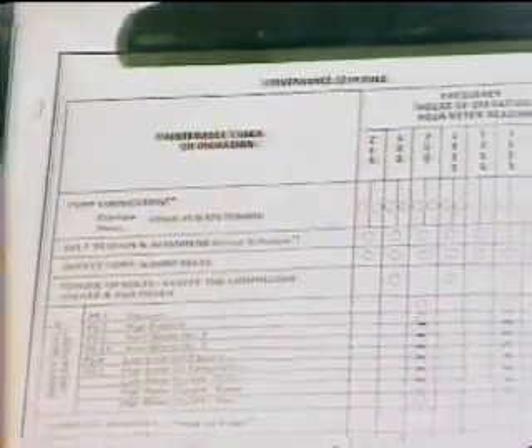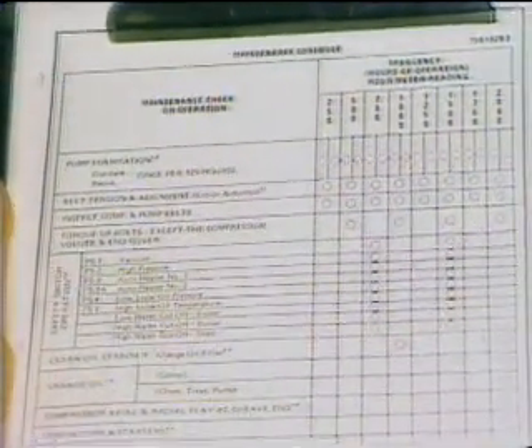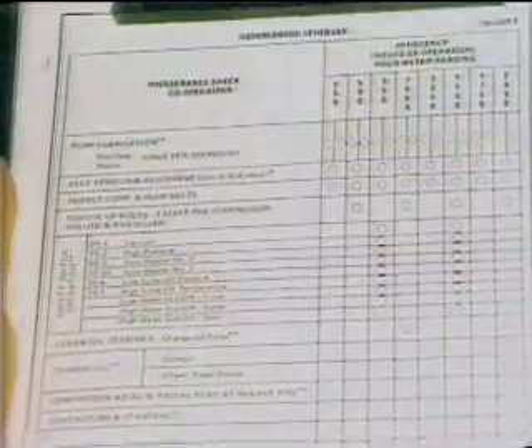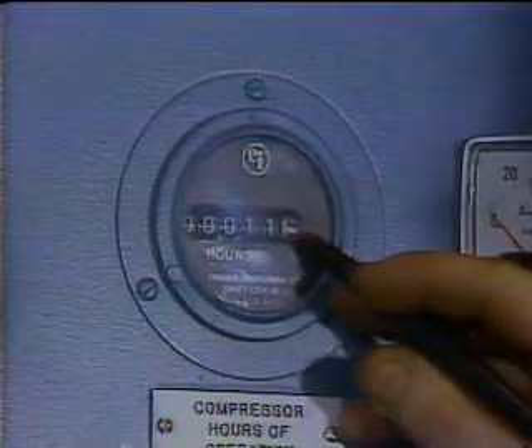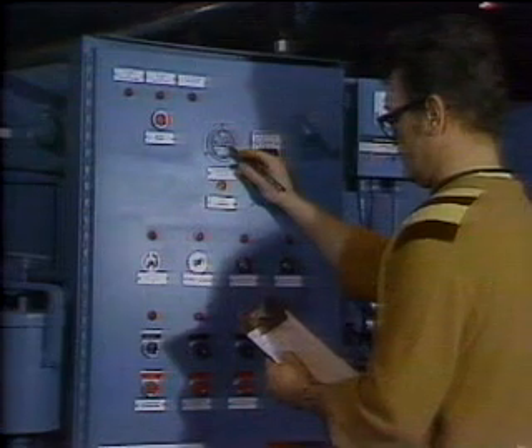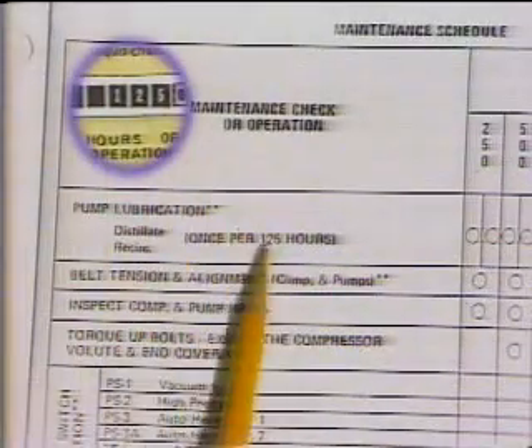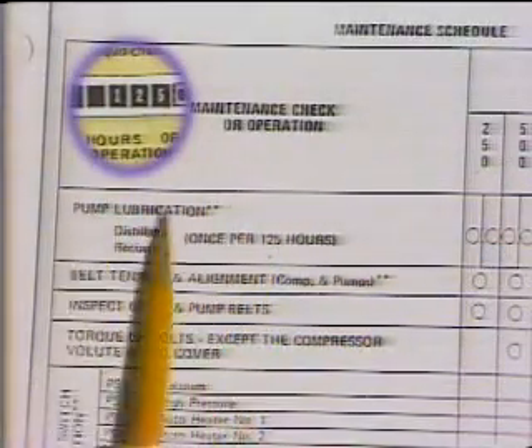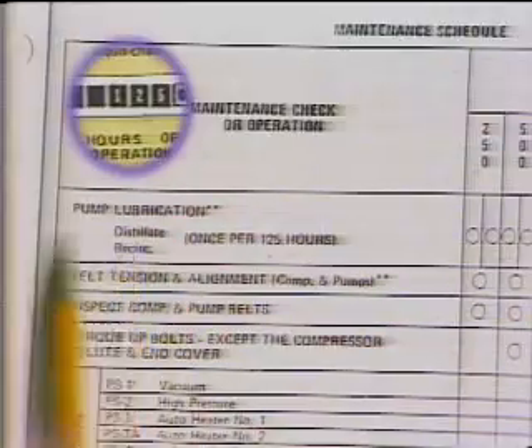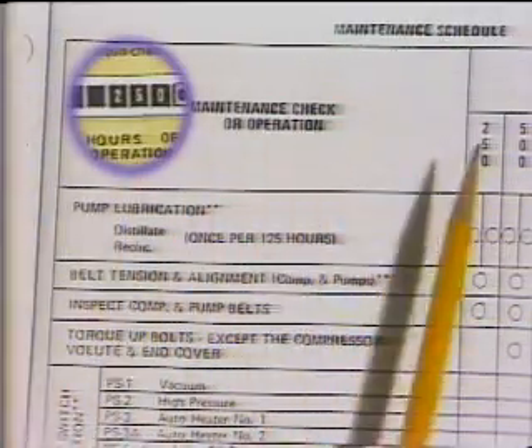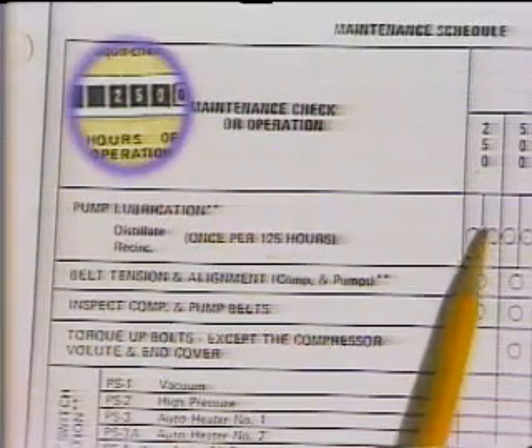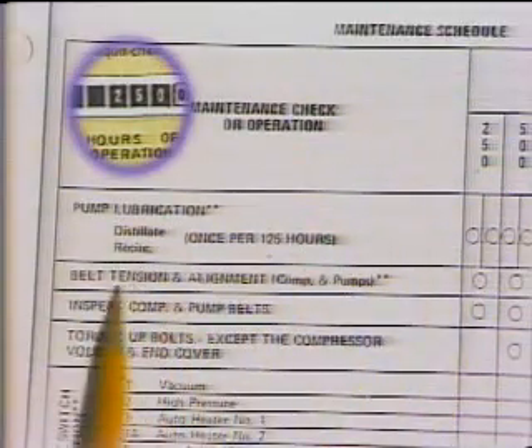A quick glance at the maintenance schedule will tell you if any maintenance is due. You should have been keeping up with this all along, in addition to your daily operational data sheets. It's real easy to keep up with. Just take the last 3 black numbers off of the hours meter. If it reads 125, you know that you need to lubricate the distillate and recirc pumps. When the meter reads 250, not only do you grease the pumps, but you also adjust your belt tension and alignment. First, the recirc and distillate belts.